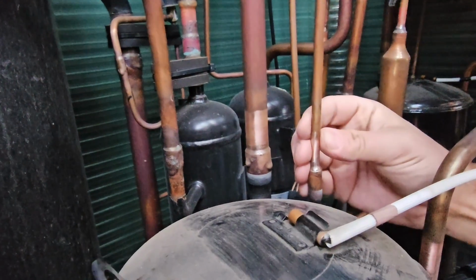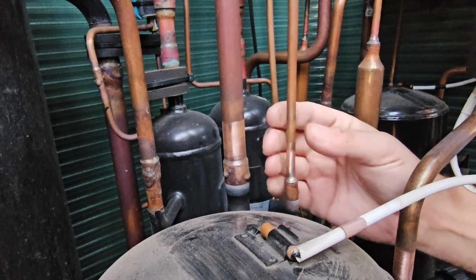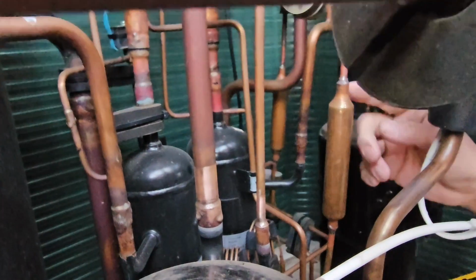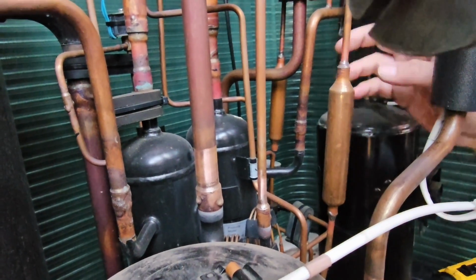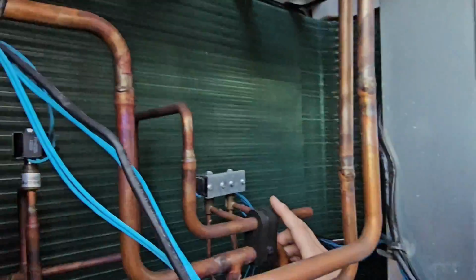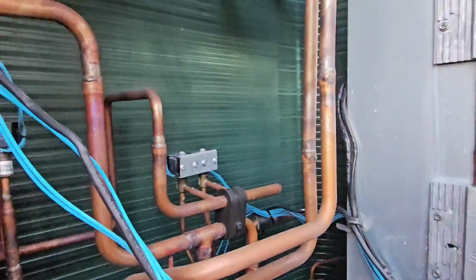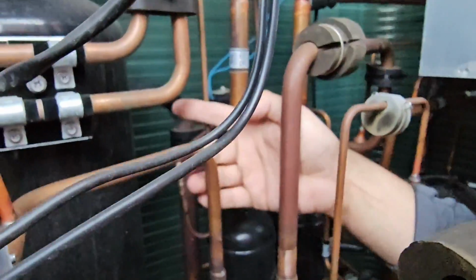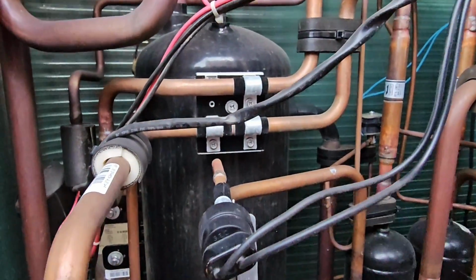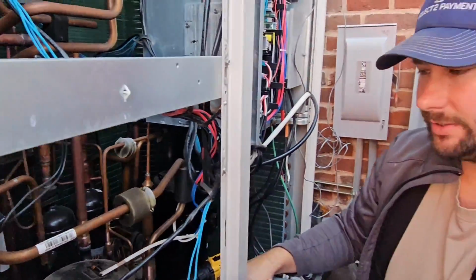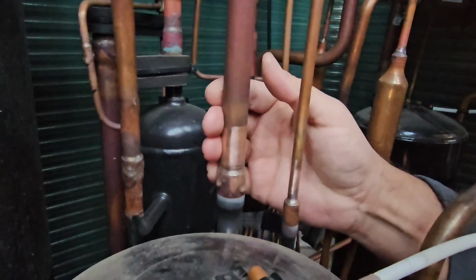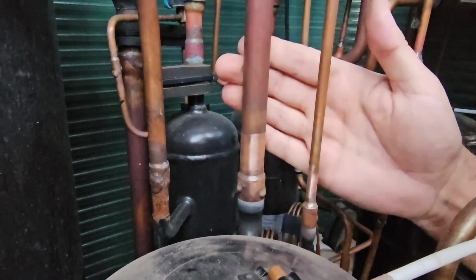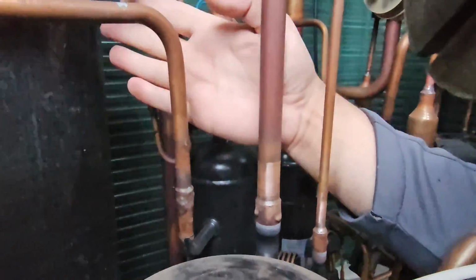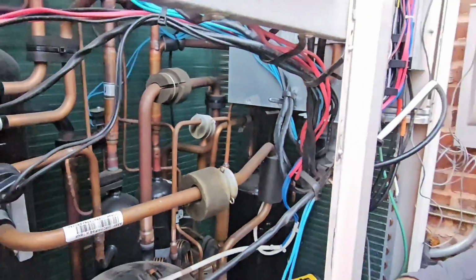Then the next pipe, this smaller 1/4 inch line, this is our oil return pipe. And if you follow this line down and then back up, it goes to these EEVs, these electronic expansion valves. And then they connect to the actual accumulator. So if we have stagnating oil, it'll return that to the compressor if it's in the accumulator. Then we've got our last pipe, which is our larger pipe, and this is our suction pipe. If you follow this line, you're going to see that it goes back into the accumulator. So those are our 3 pipes. I'm going to go ahead and cut those.